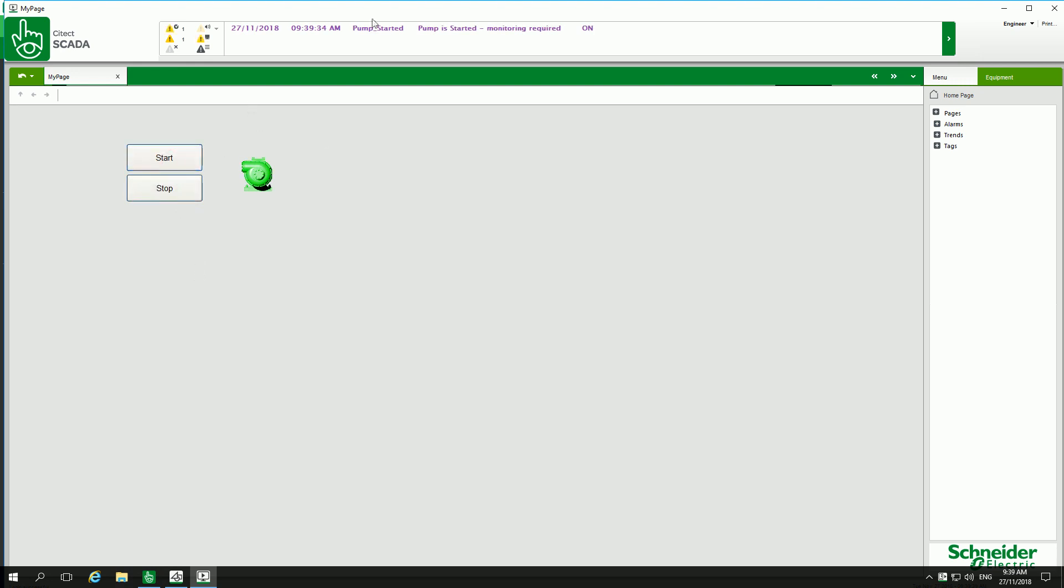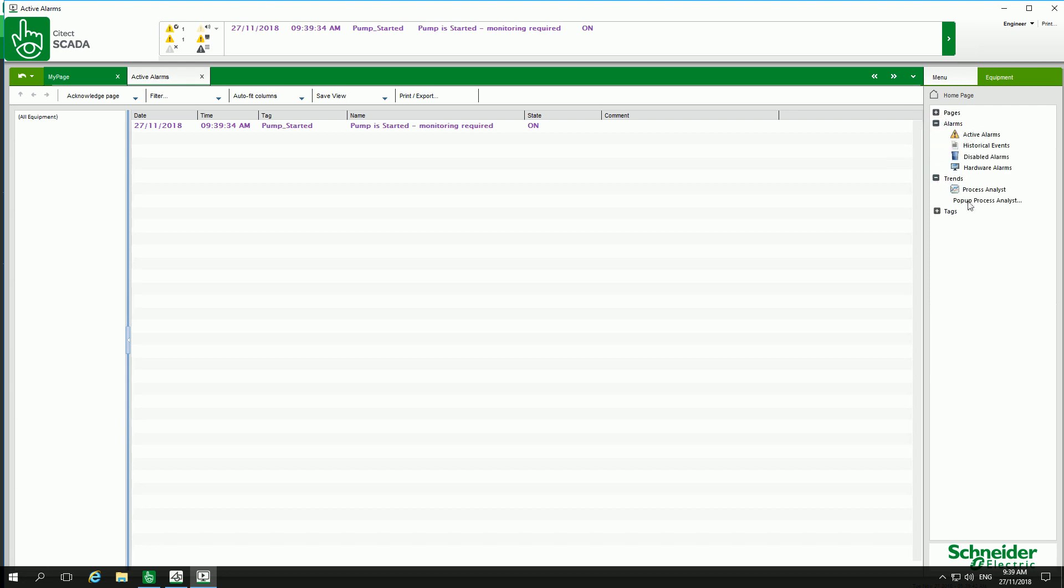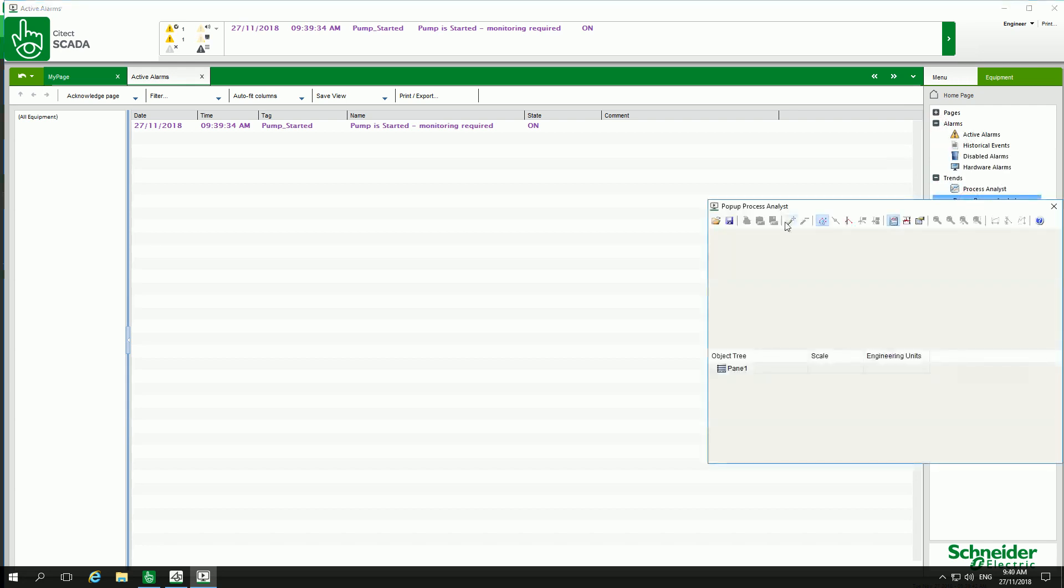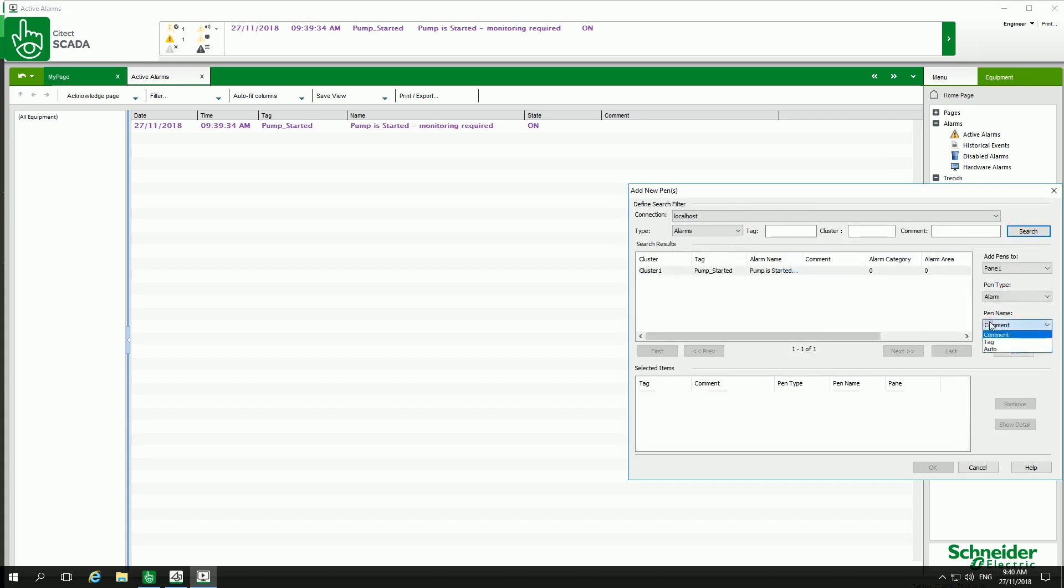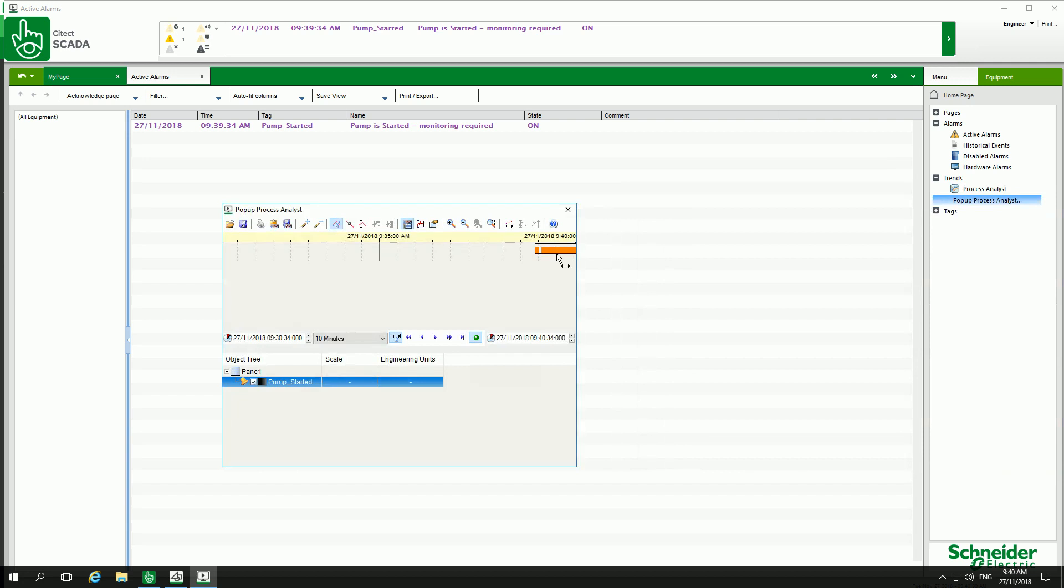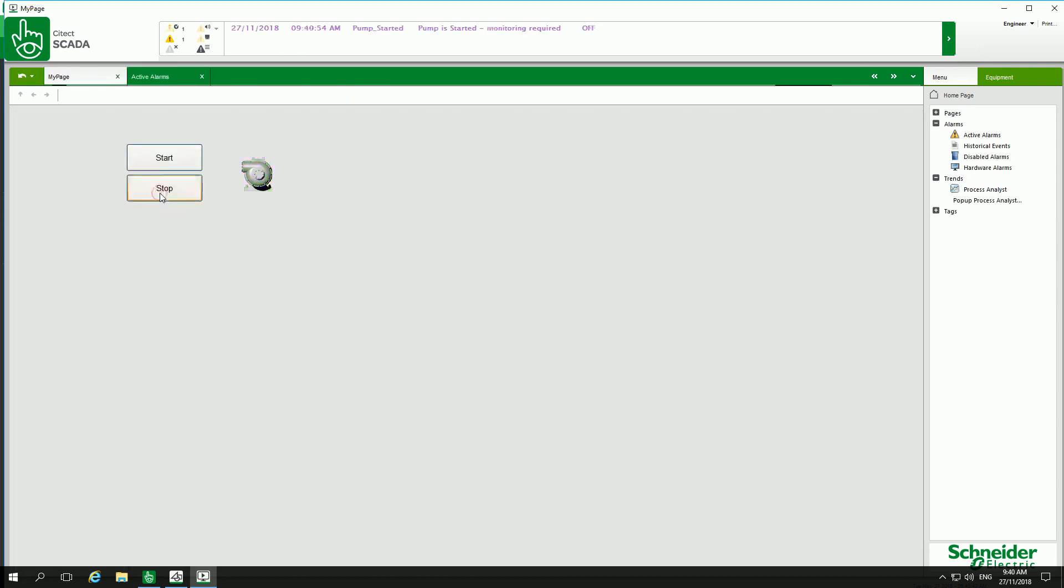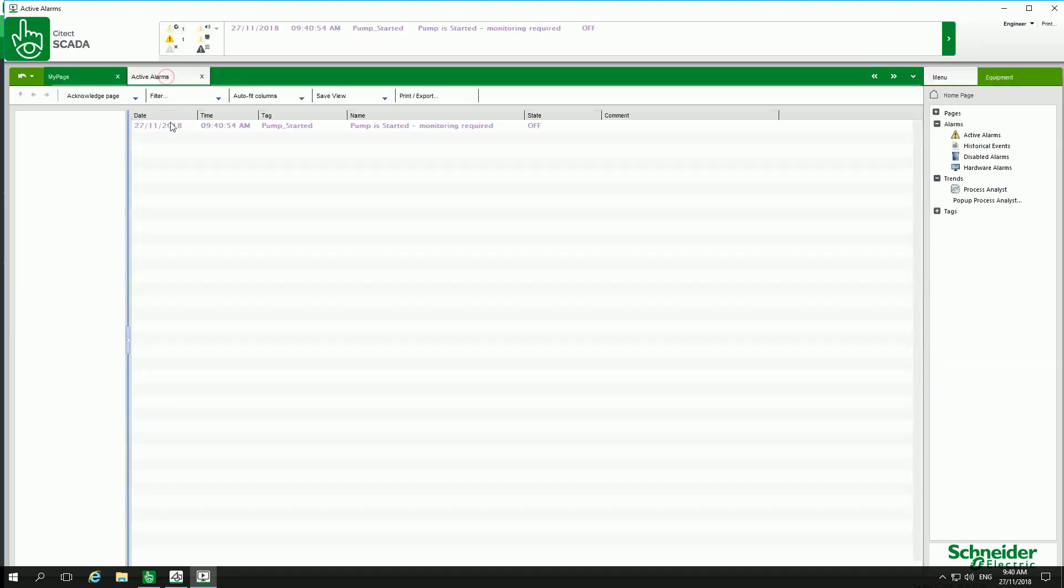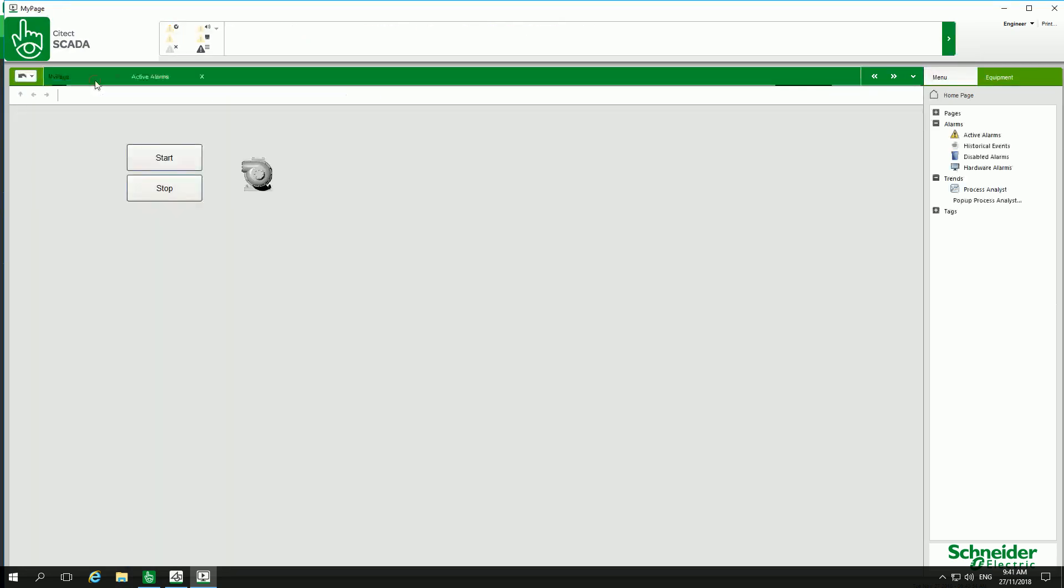If I want to see more about the alarm, I can click on this logo or I use this shortcut. For the trend, I can open my alarm and the trend search for the name, add these tags here, and we can see the value of my tag changed a couple of times. Actually, now it's equal to 1, so that means my pump is started, so I can stop it. If I go back to the alarm page, I can acknowledge my alarm.